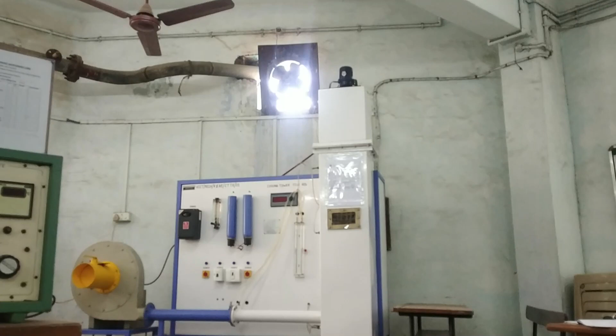Now we will see the fan location. On the top side, a fan is located, and on the bottom side there is a blower. If the bottom one is turned on, it becomes a forced draft cooling tower. If that is turned off and we turn on the fan on the top instead, it becomes an induced draft cooling tower.